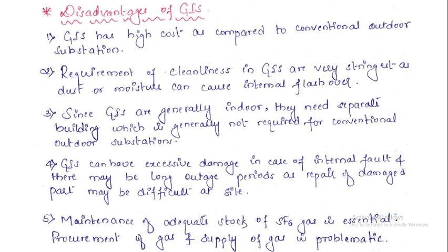on the ground. GIS can have excessive damage in case of internal fault, and there may be long outage periods, as repair of a damaged part may be difficult at a site. As these are placed indoors inside the building, repairing the parts becomes very difficult. If I want to remove or take away parts of the substation, it becomes a little difficult and will create a lot more damage to the other equipment also.